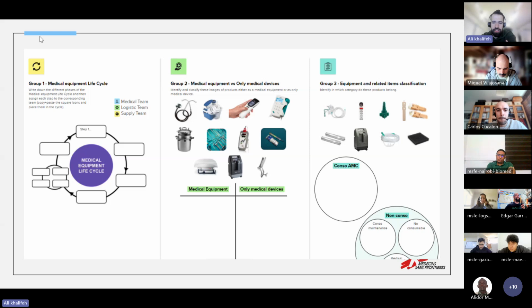Yeah. Just to explain, in MSF, usually they are medical equipment. We have the medical intersectional guideline, biomedical, but it's equipment, physical machines and devices that are used for patient care. So any equipment like the thermometer, the balance, they are used for medical care. We are taking some parameter from them to identify, for example, the balance: we need the weight to identify the dose of some medication to give the patient. The thermometer, we are taking the temperature, and based on this temperature, we can do some clinical treatment. So any equipment needs preventive and corrective maintenance, power, installation, spare parts, and calibration validation. They are classified as medical equipment. I don't know if it's clear or not.